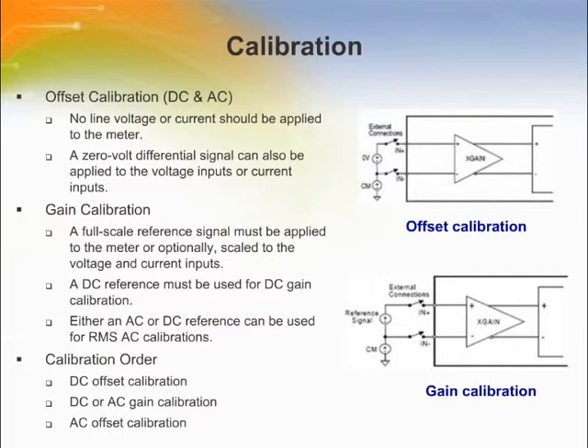During offset calibrations, no line voltage or current should be applied to the meter. A zero voltage differential signal can also be applied to the voltage inputs or current inputs. During gain calibration, a full-scale reference signal must be applied to the meter or optionally scaled to the voltage and current inputs. A DC reference must be used for DC gain calibration. Either an AC or DC reference can be used for RMS AC calibrations. If DC is used, the associated high-pass filter must be off.